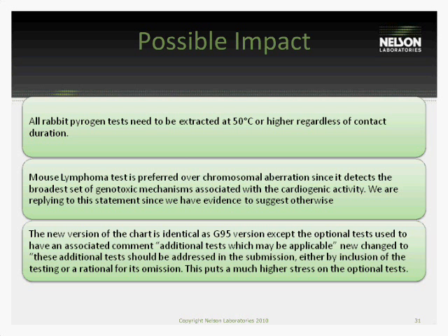Here we don't have that kind of out, where if the device changes chemically. For me specifically, there are some compounds that at 50 degrees might actually start to degrade and become more viscous in solution. And we're, once again, not really allowed to manipulate, as far as centrifuge or filter, that extract. And we all know that if injecting a slightly viscous solution IV into a rabbit, we could have some material pyrogen that's not actually from the device, but just from a mechanical reaction from that extract. So we're asking for some clarification there: if the device changes physically or chemically at 50 degrees, can we still use 37 degrees for the rabbit pyrogen test?